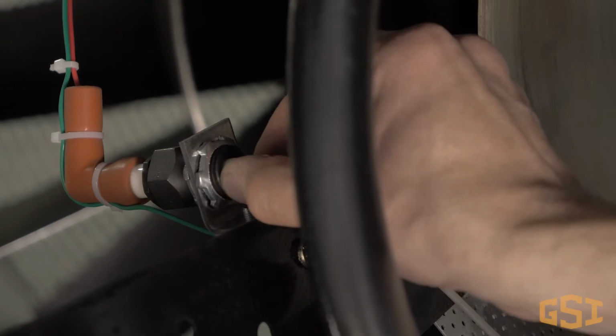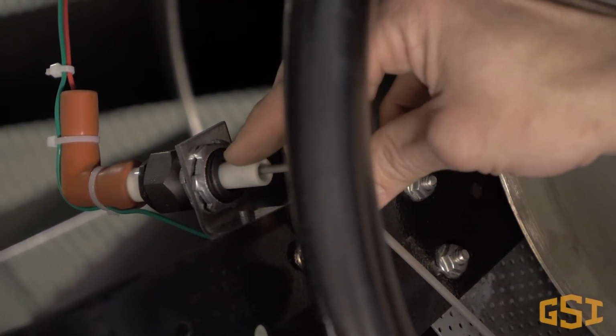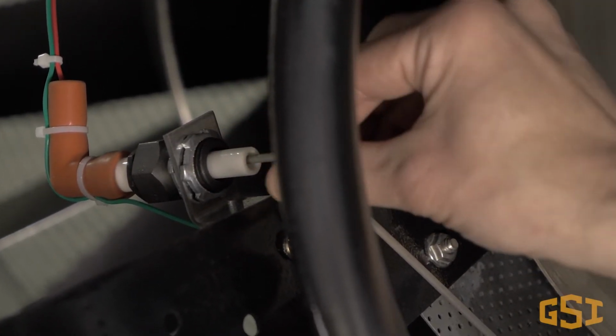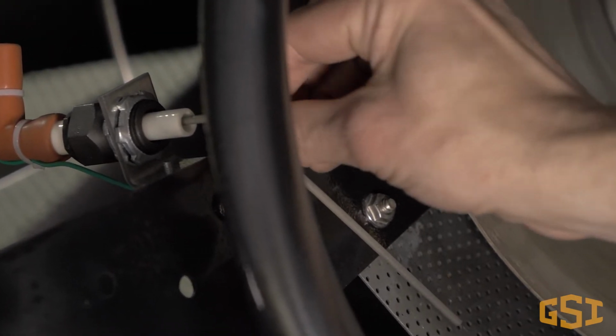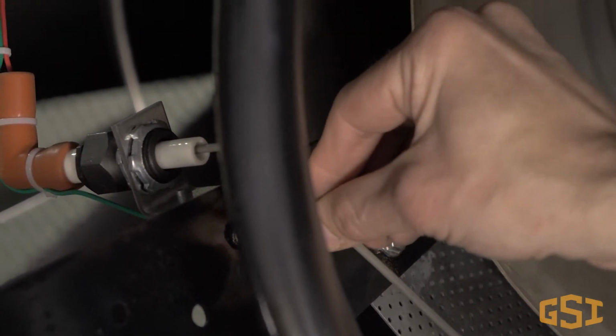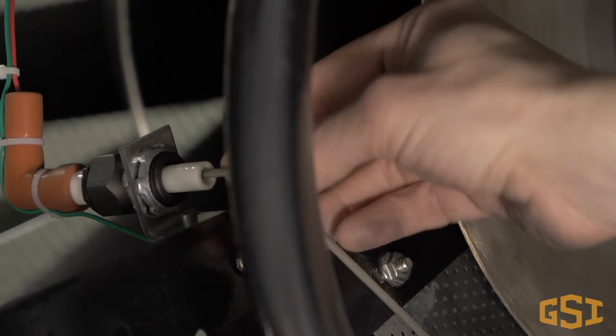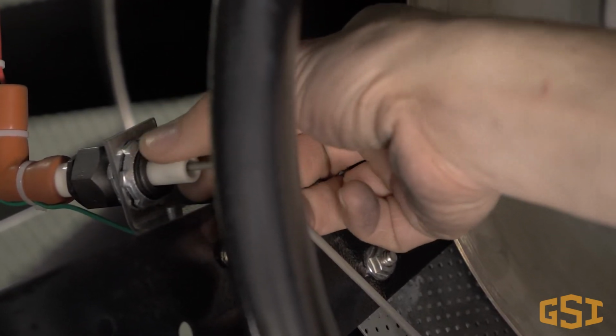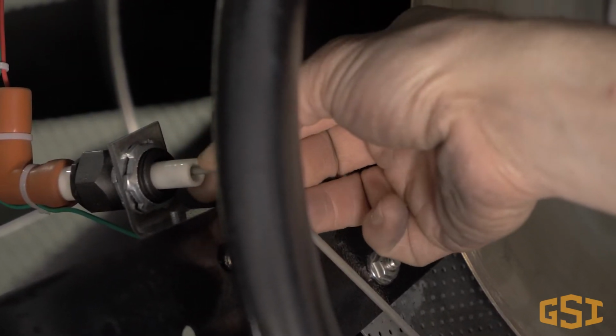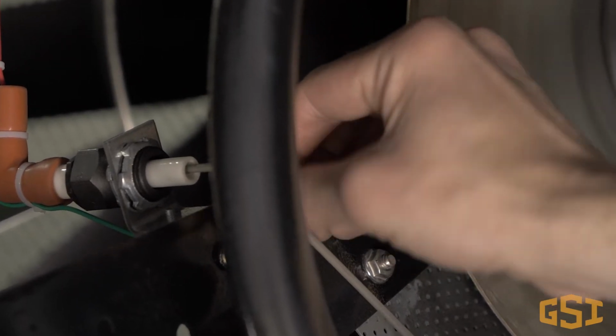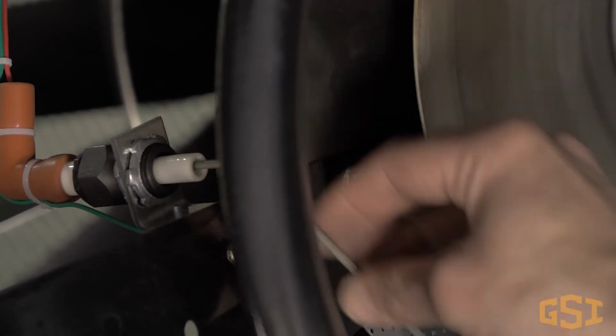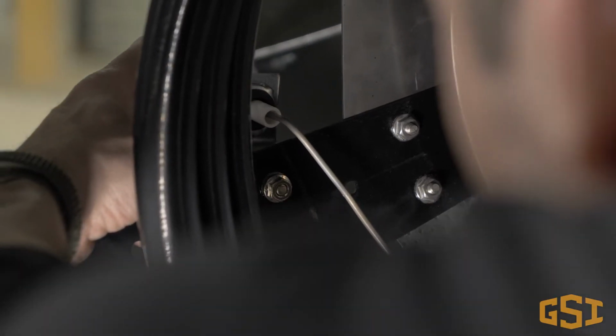Finally, let's look at the flame probe itself. Visually inspect the flame probe. Look for cracks in the porcelain base. Is the flame probe secure in the porcelain? Is the probe clean without buildup? If necessary, use emery cloth to polish the metal probe. Do an overall inspection of the probe and then ensure that it is tight in the flame probe mount.